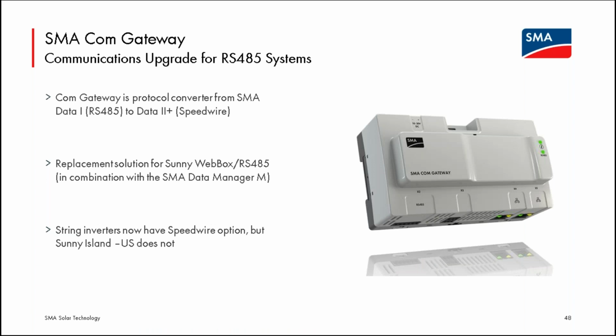I don't want to spend too much more time on the presentation, to give time for questions, but one thing that is unfortunately a bit of a pain point for the Sunny Island US right now is the communication structure. The Sunny Island US only has RS-485 as a communication choice. All of our other inverters, our PV inverters, the Sunny Boy storage battery inverter, now speak over an Ethernet communication-based protocol. So if you have Sunny Islands and Sunny Boys in the same system, there has to be a translator from the RS-485 of the Sunny Island to the Ethernet-based protocol that the Sunny Boys will use, and it is required for sending data to our Sunny Portal.